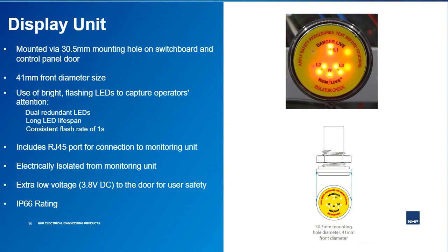As you can see from the image, the display unit makes use of fairly bright LEDs designed to capture the user's attention on the presence of live voltage. Each phase is represented, that's L1, L2, and L3, as well as neutral, so that the operator is provided info on potential difference between the various conductors being monitored. Each of the phases is represented by dual redundant LEDs, although the LEDs used have a long lifespan and overall reliable quality. In case of failure, there is an LED for backup for each of the three phases.